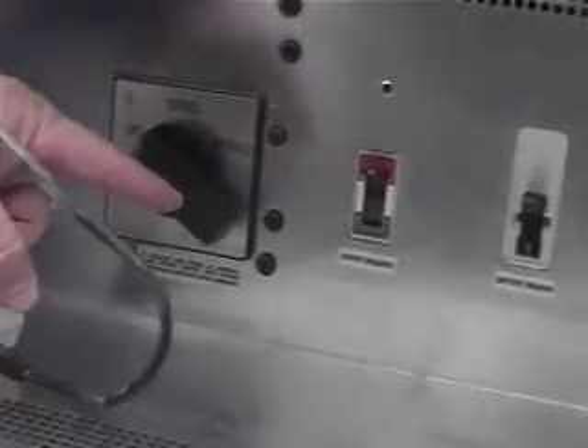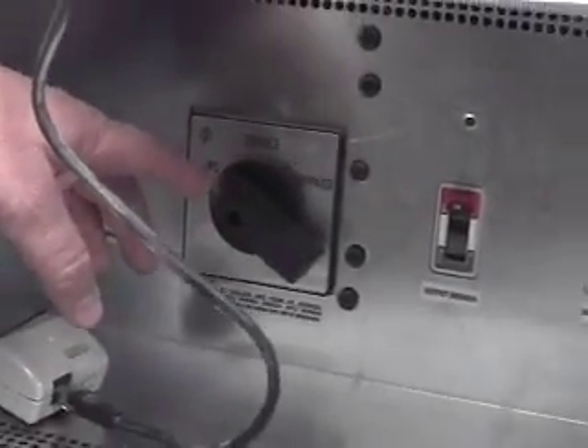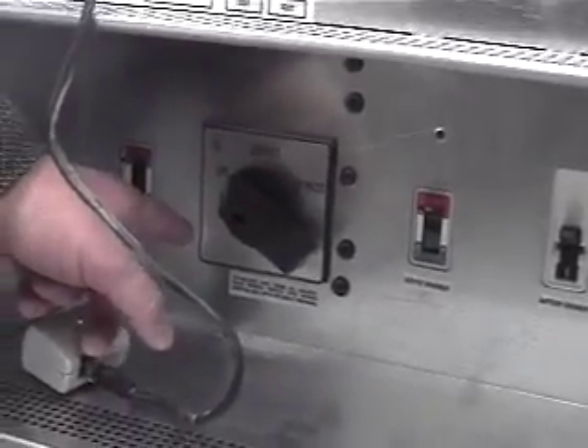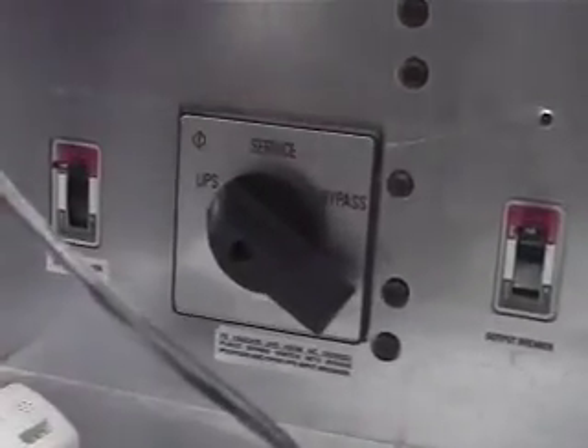For the normal startup on this unit, we've already removed the front panel. It's verifying the position of the rotary switch. Right down here, there's a UPS, a service, and a bypass position. So if you're starting this thing up from scratch, you're going to want to make sure it's in the UPS mode, right there.